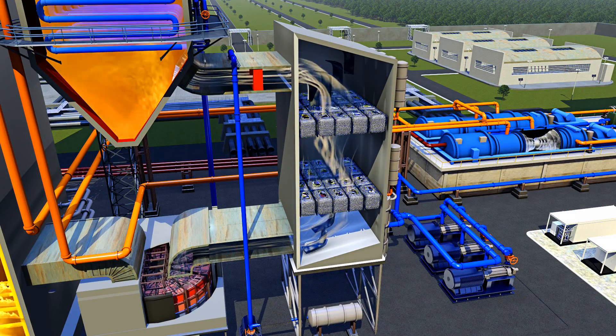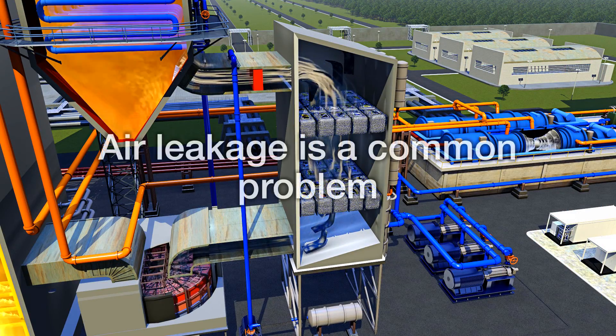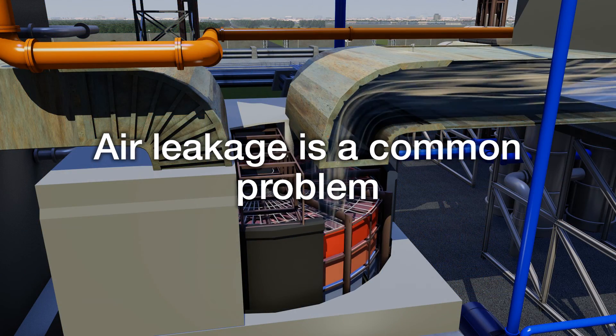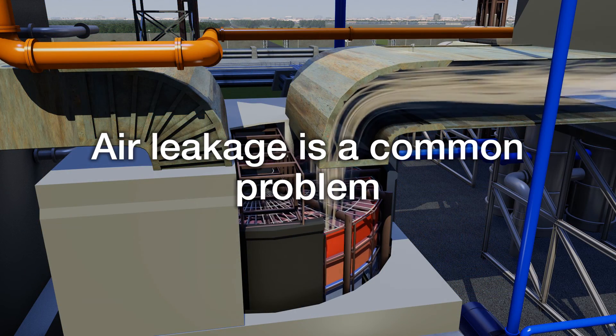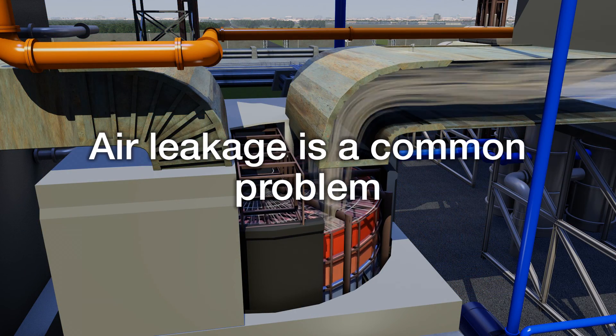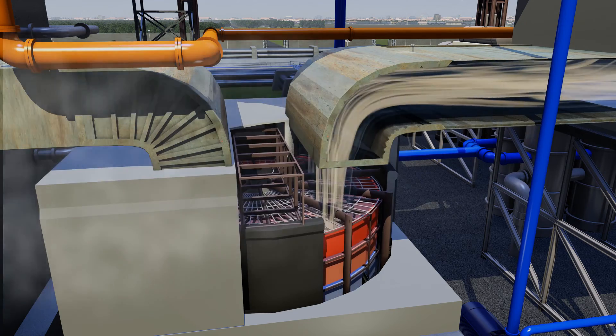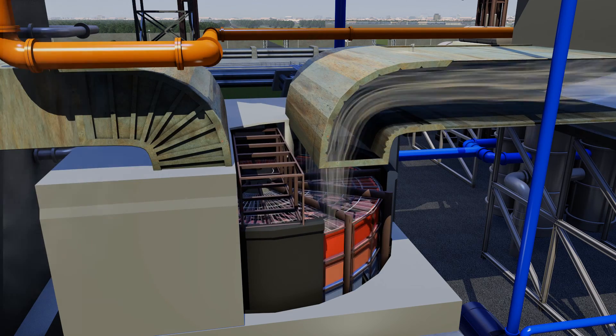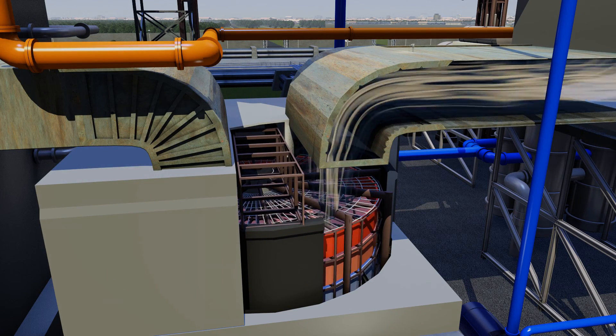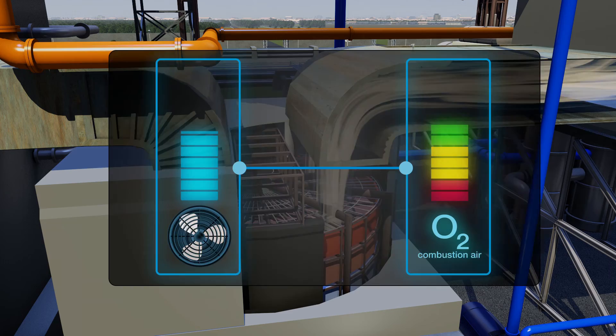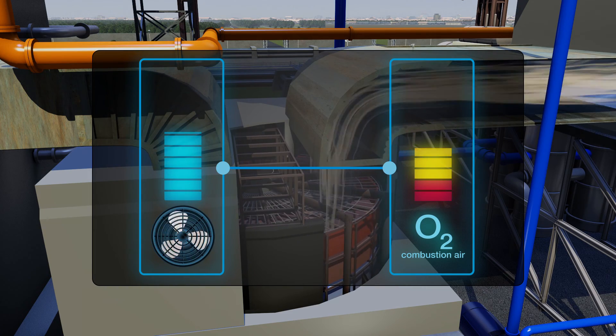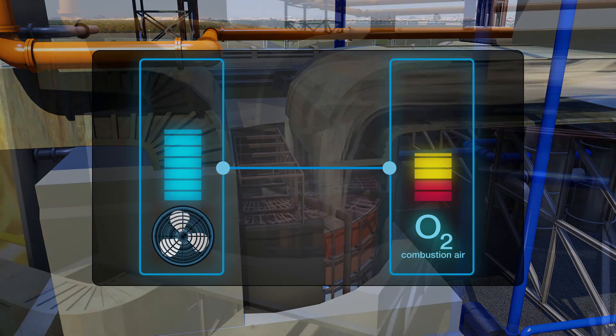In installations using rotary air preheaters, a common problem is air leakage caused by deterioration of the heater seals, which divide the sectors. Combustion air leaking across to the flue gas stream must be compensated for by an overall increase in the amount of air being moved by the forced draft, or FD fan.